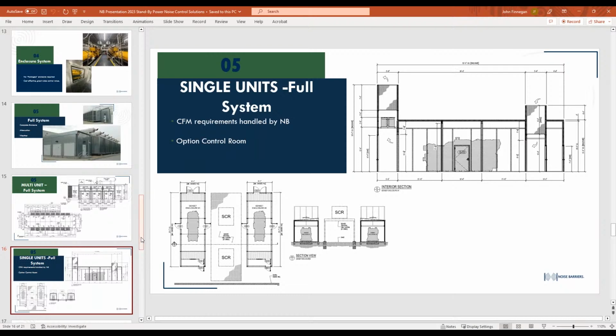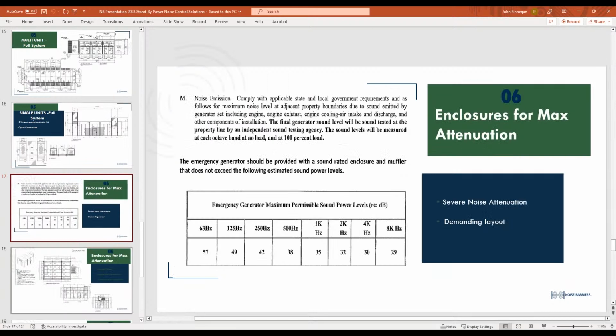So this is for a single system. This is when we absolutely know, much like in the barn style, but here we're really tuning it to that specific engine - what its CFM is, what its pressure drop is, what the horsepower of the motor is, what the heat buildup is in there. All of that is part of our design package. These are snippets from what our typical submittal would look like, 10 to 12 pages with multiple details that usually go to an engineering group for the mechanical side of it.